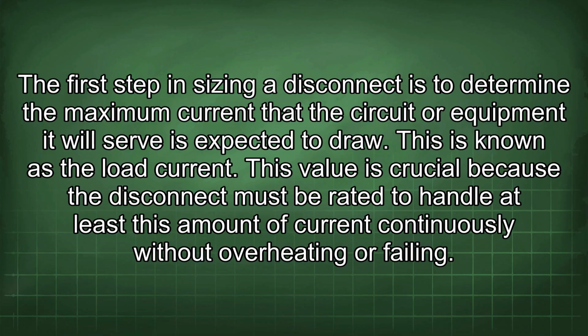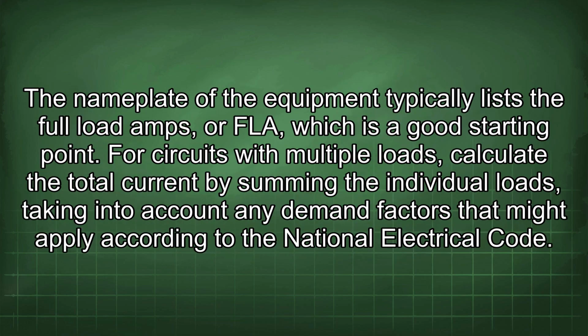This value is crucial because the disconnect must be rated to handle at least this amount of current continuously without overheating or failing. The nameplate of the equipment typically lists the full load amps, or FLA, which is a good starting point. For circuits with multiple loads, calculate the total current by summing the individual loads, taking into account any demand factors that might apply according to the National Electrical Code.